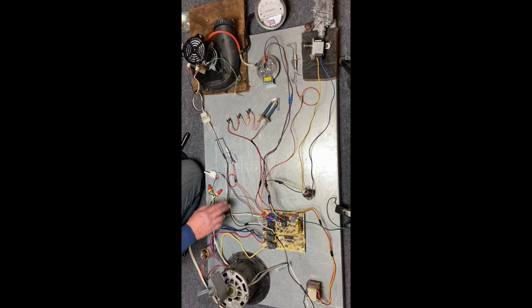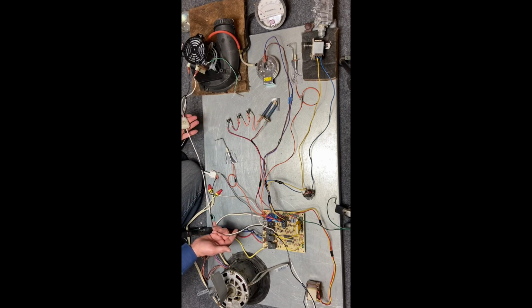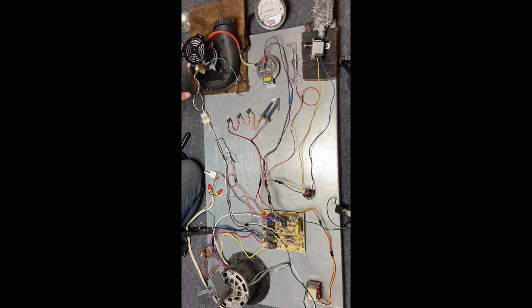Now we're going to go through a little bit more. These 2 plugs are actually following all the way to our inducer fan motor, or our induced draft motor. 2 wires to the motor, so if I want to see if this motor is not working, do I have voltage to the motor? So it goes all the way back to here. Do you have voltage here? Yes. Do you have voltage here? Yes. Motor's not turning? Well, we have a bad motor. So we energize this motor.